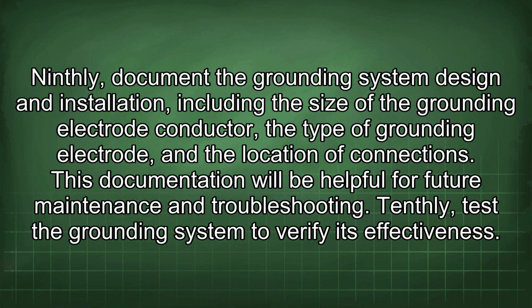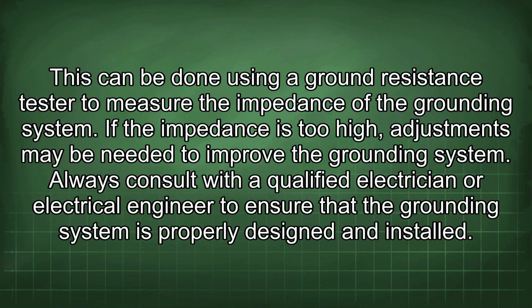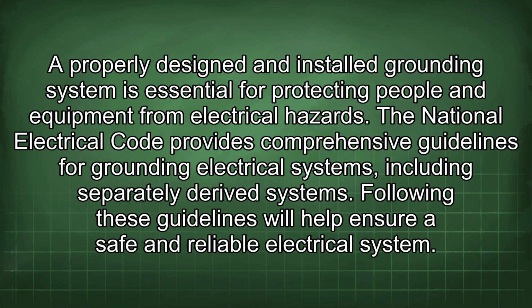Tenthly, test the grounding system to verify its effectiveness. This can be done using a ground resistance tester to measure the impedance of the grounding system. If the impedance is too high, adjustments may be needed to improve the grounding system. Always consult with a qualified electrician or electrical engineer to ensure that the grounding system is properly designed and installed. A properly designed and installed grounding system is essential for protecting people and equipment from electrical hazards.